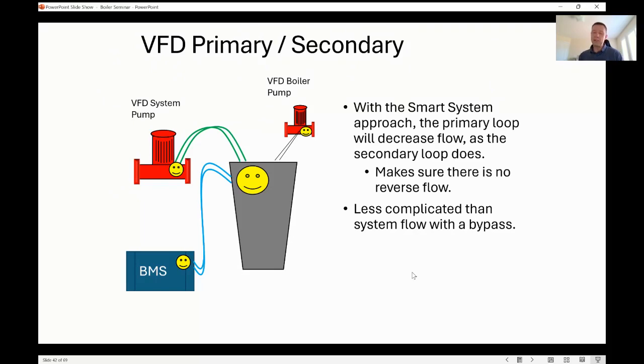I'll have a BMS, or maybe my onboard controls will do the indoor-outdoor reset. That determines the set point. So here, let's say we have a building management system that says, hey, boiler, I need 150 degrees. Okay, I will lead-lag my plant to give you 150 degrees. This is more of a macroscopic control. Then I'll have the VFD system pump saying, hey, there's less load on it.